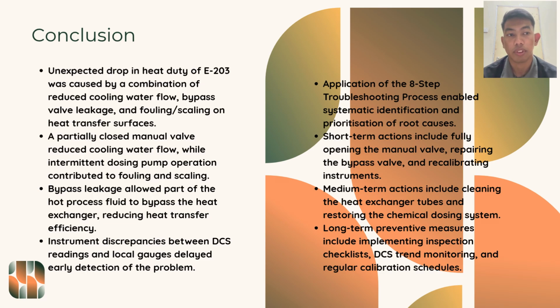Application of the 8-Step Troubleshooting Process enables systematic identification and prioritization of root causes. Short-term actions include fully opening the manual valve, repairing the bypass valve, and recalibrating the instrument. Medium-term actions include cleaning the heat exchanger tubes and restoring the chemical dosing system. The long-term preventive measures include implementing inspection checklists, DCS trend monitoring, and regular calibration schedules.